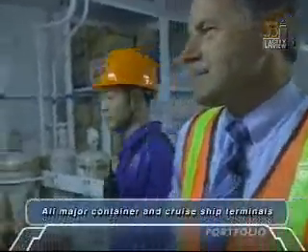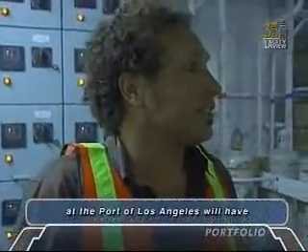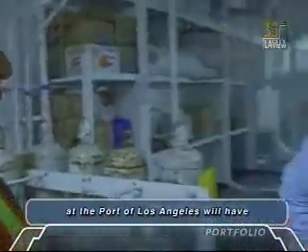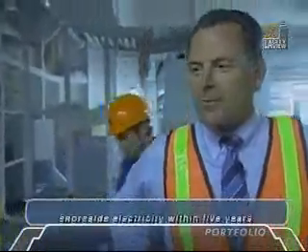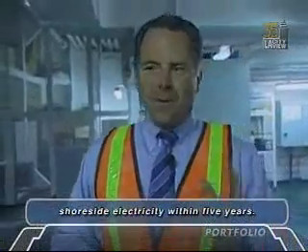2 megawatts. And what does that mean exactly for the clean air? What's the benefit for us? Well, it's really fantastic. When the ship is connected to shore power during the port stay, we're basically saving about a ton of emissions: NOx, SOx, and diesel particulate matter, all combined about a ton on a per vessel port call. But more importantly, we're also saving on greenhouse gases, about 4 tons of greenhouse gases with a ship of this size.